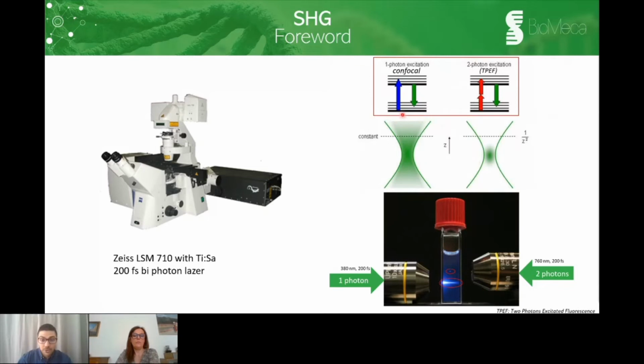When we use a confocal microscope, a photon excites the electrons of the fluorophore by hitting it at the excitation wavelength, then the electron reaches an excited state, and when it comes back to its ground state, there is a loss of energy released as a photon of light. In contrast, when we use multiphoton microscopy, the first photon hits the probe electron at twice the excitation wavelength. It reaches an intermediate state, and then a hit of the second photon puts the probe in the excited state. And when the electrons come back to the ground state, there is a loss of energy released as a photon of light.